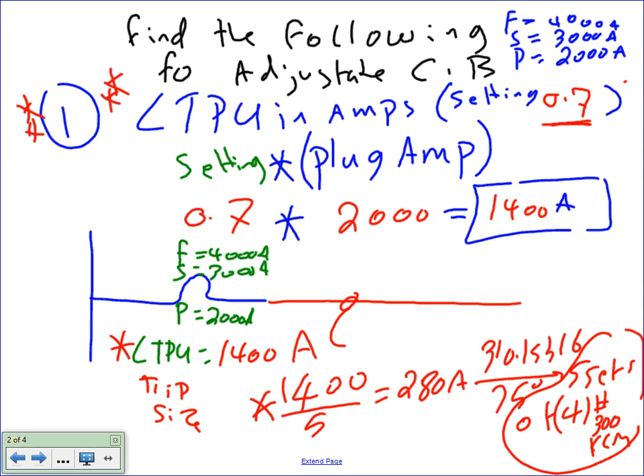So on the test, guys, I'm going to ask you first to find the long time pickup, and second to size the cable. When you look at the circuit breaker, it's going to have 4 amp ratings: one is the frame, one is the sensor, one is the plug, and one is the long time pickup, or the trip. When you size the conductor, you always size it based on the trip size or the long time pickup. That's it.